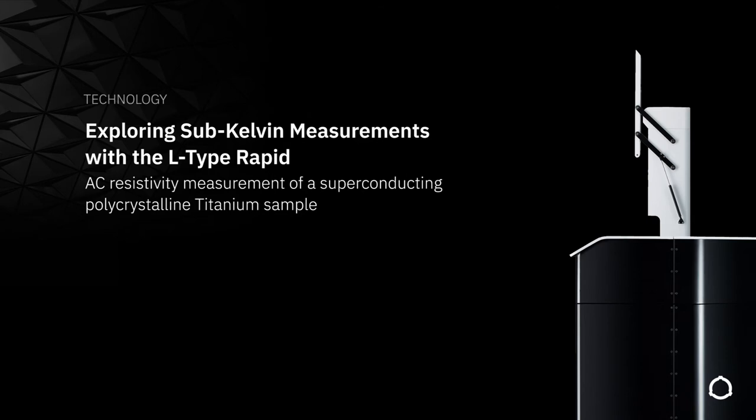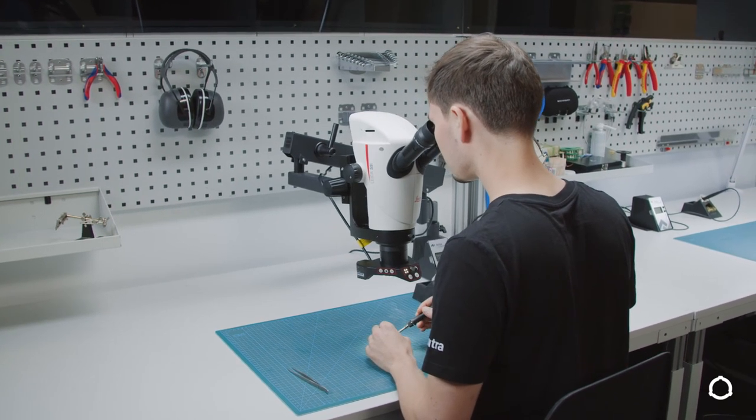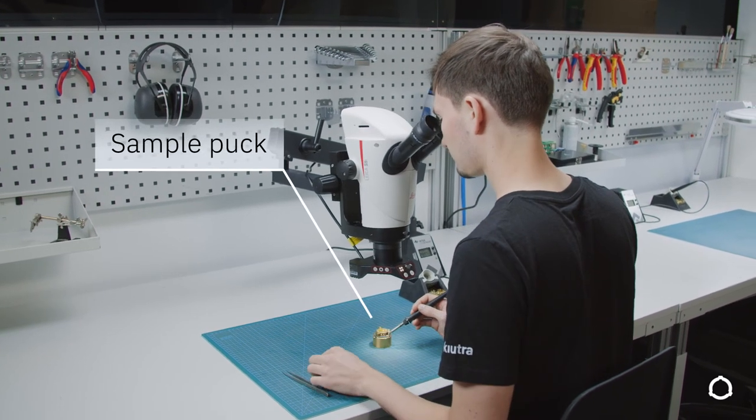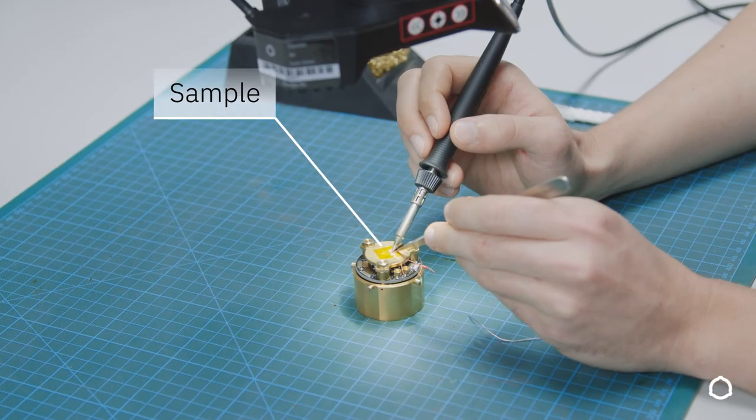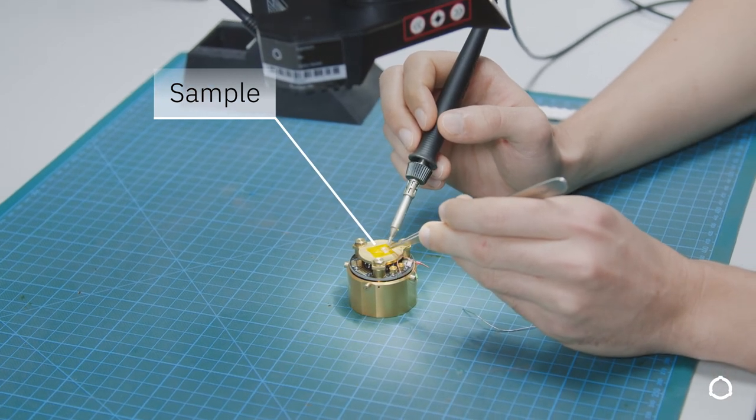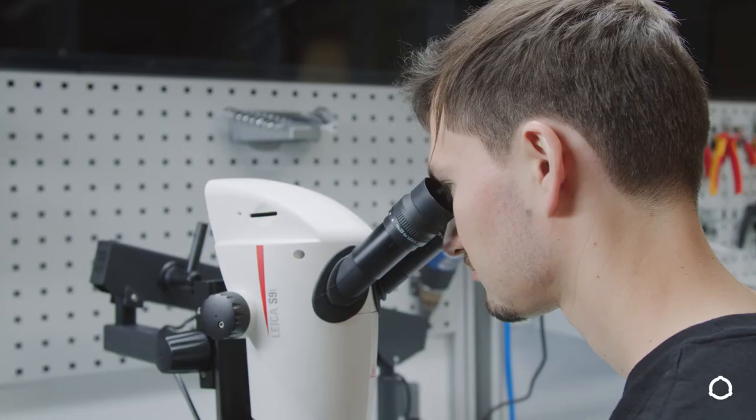Now in the last part of this webinar, I would like to demonstrate how to use the L-Type Rapid and our instrument control and measurement software for a simple low-temperature experiment. I will demonstrate how to carry out an AC resistivity measurement on a titanium sample, where we track the superconducting transition at around 500 mK and suppress the transition by the application of an external magnetic field. The L-Type Rapid features our puck-based sample transfer mechanism, so the first thing to do is to prepare the sample on the sample puck. The sample puck has a platform which can accommodate customer setups and samples of up to 36 mm in diameter and 100 mm in height. The puck connects 40 DC lines via bondable terminals as well as up to 4 additional RF lines via mini-SMP connectors.